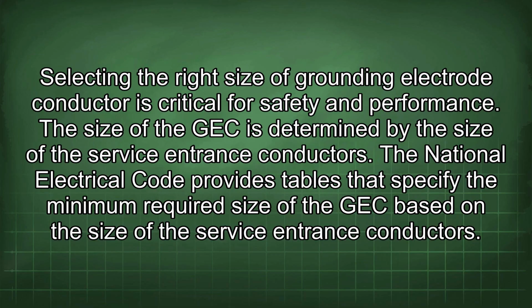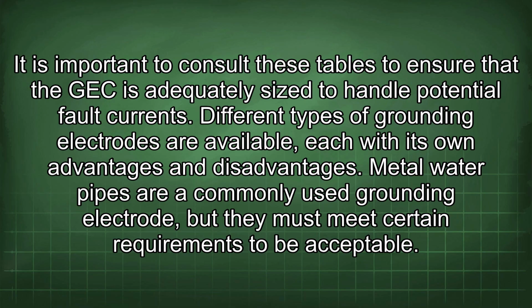Selecting the right size of grounding electrode conductor is critical for safety and performance. The size of the GEC is determined by the size of the service entrance conductors. The National Electrical Code provides tables that specify the minimum required size of the GEC based on the size of the service entrance conductors. It is important to consult these tables to ensure that the GEC is adequately sized to handle potential fault currents. Different types of grounding electrodes are available, each with its own advantages and disadvantages.